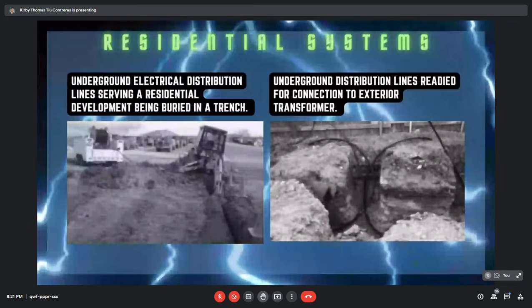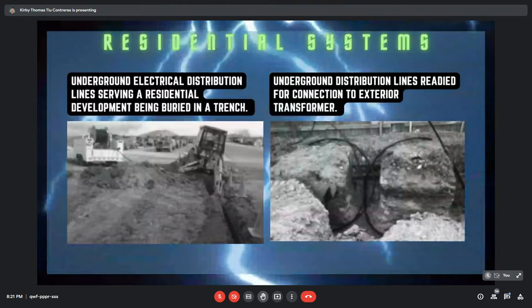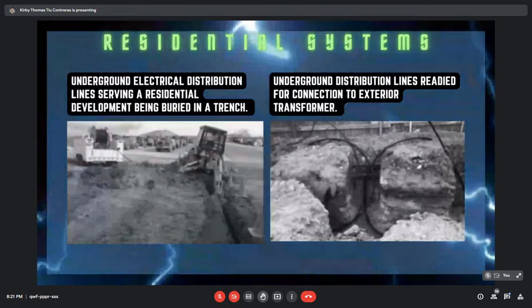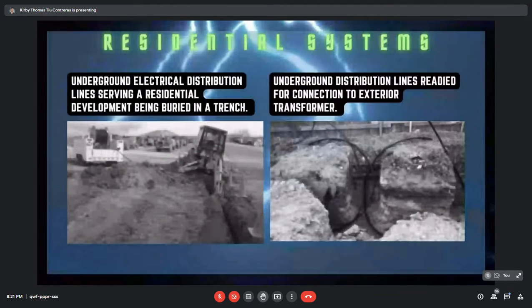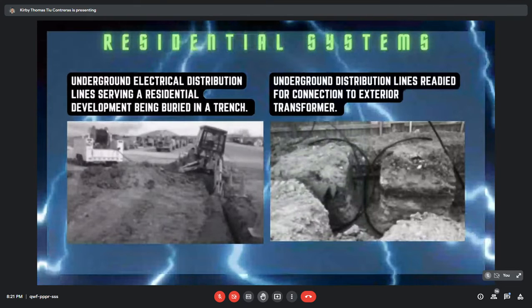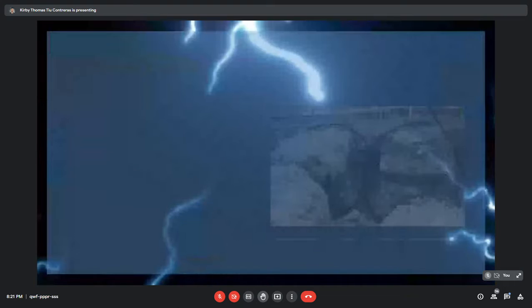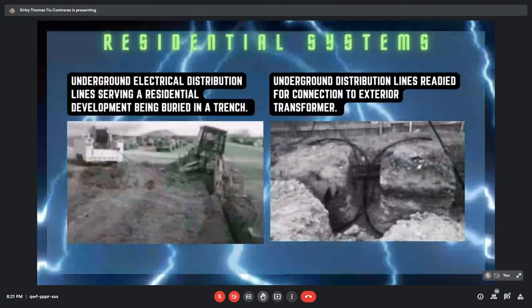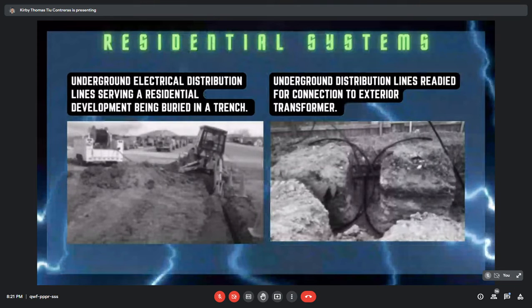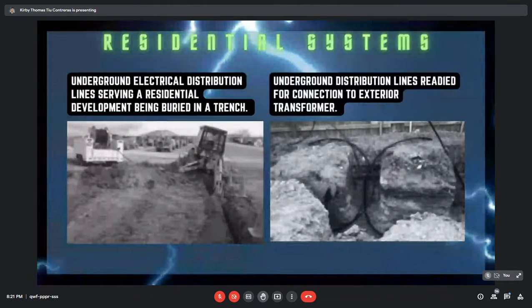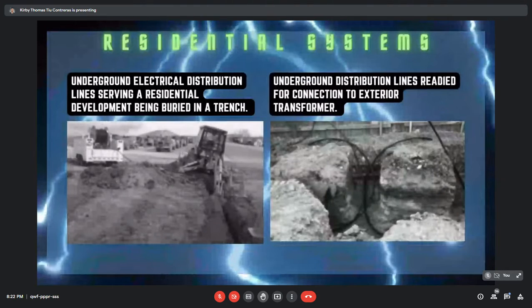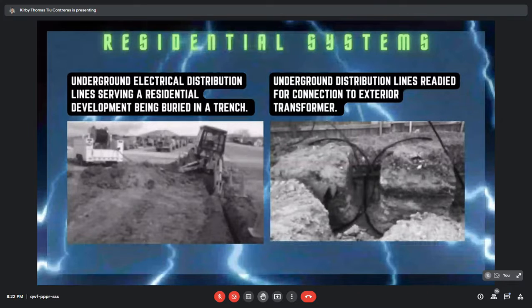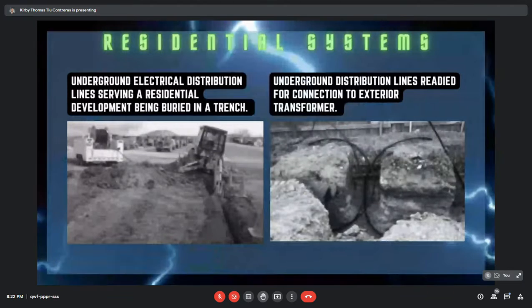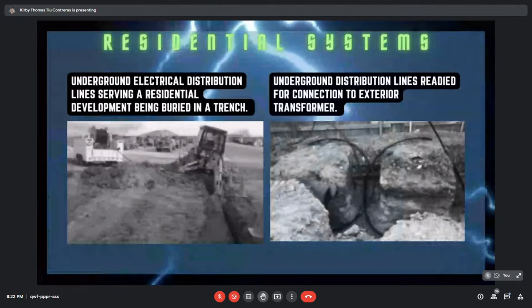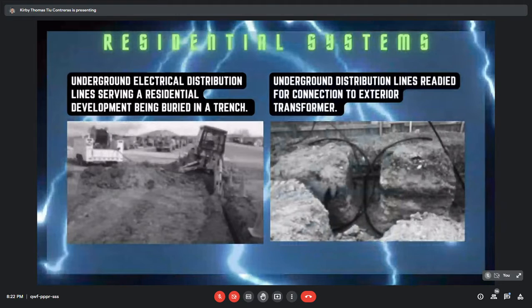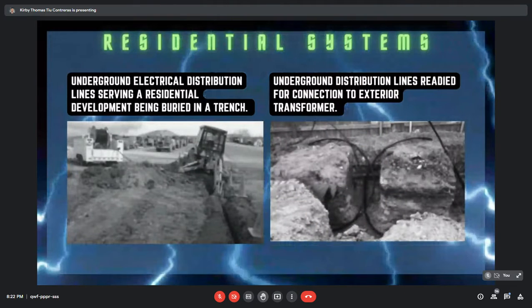The first picture shows the underground electrical distribution lines serving a residential development being buried in a trench. The second picture shows the underground distribution lines needed for connection to an exterior transformer. If you are wondering where this underground wiring system is commonly used, here is the answer. Underground cables are usually used in urban areas where local or state regulations override economic considerations, such as airports. So we see this underground wiring system in airports, where an overhead line may endanger lives. So, next slide please.